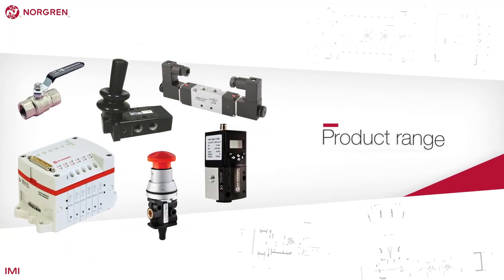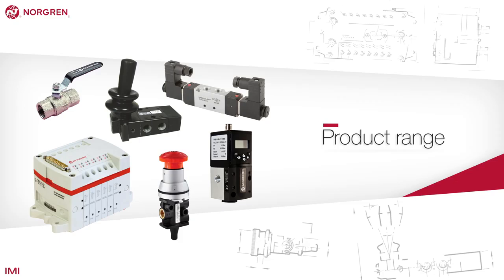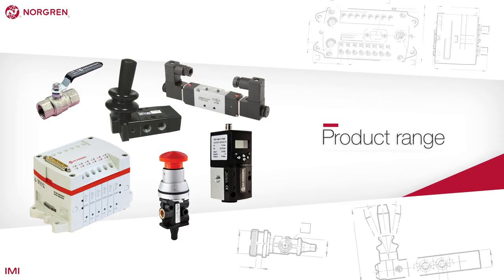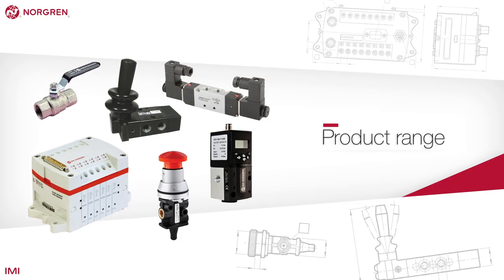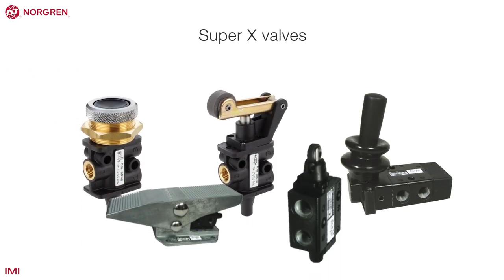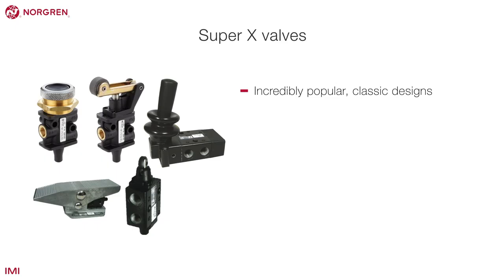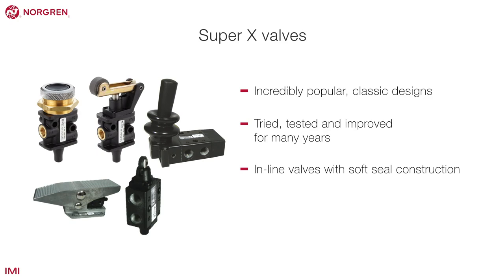Now we have learnt about the theory, let's take a look at some of the control valves in the product range. Super X manual and mechanical valves are incredibly popular classic designs that have been tried, tested, and improved for many years, making them extremely reliable. All are inline valves with soft seal construction and have an operating pressure from vacuum to 10 bar or 145 psi.